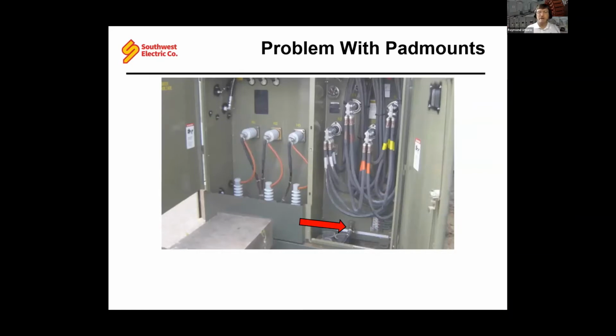If you can access that, even if you're suited up, it is not recommended to sample this energized. You can certainly, but you're so close to these power cables that it would certainly be risky. And so most of the time, sampling requires a de-energization of that transformer. That would be the safest way to do it. But going back to our first slide, those 11 days of outage is all you're allowed per year. So it does make this sampling more difficult. You want to do sampling on a fairly regular basis.